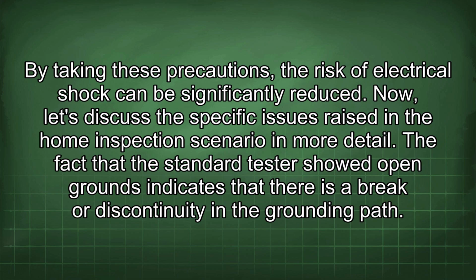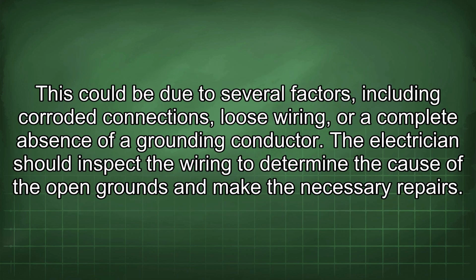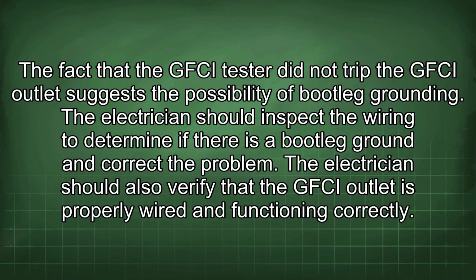Now, let's discuss the specific issues raised in the home inspection scenario in more detail. The fact that the standard tester showed open grounds indicates that there is a break or discontinuity in the grounding path. This could be due to several factors, including corroded connections, loose wiring, or a complete absence of a grounding conductor. The electrician should inspect the wiring to determine the cause of the open grounds and make the necessary repairs. The fact that the GFCI tester did not trip the GFCI outlet suggests the possibility of bootleg grounding. The electrician should inspect the wiring to determine if there is a bootleg ground and correct the problem. The electrician should also verify that the GFCI outlet is properly wired and functioning correctly.